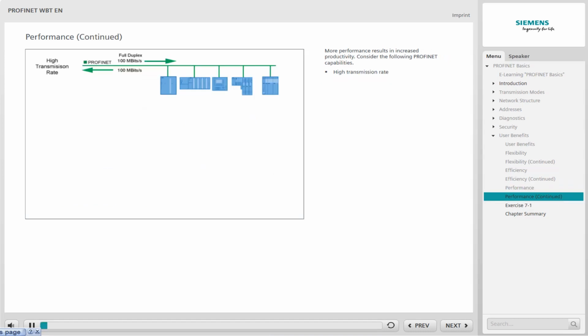By using Ethernet in full duplex mode, PROFINET achieves a significantly higher transmission rate than field buses, allowing both process data and other plant data to be quickly transferred via TCP without any problem. The data rate of PROFINET with full duplex capability is approximately 18 times higher than with PROFIBUS, allowing data-intensive applications on the backbone to quickly and efficiently exchange plant and production data.